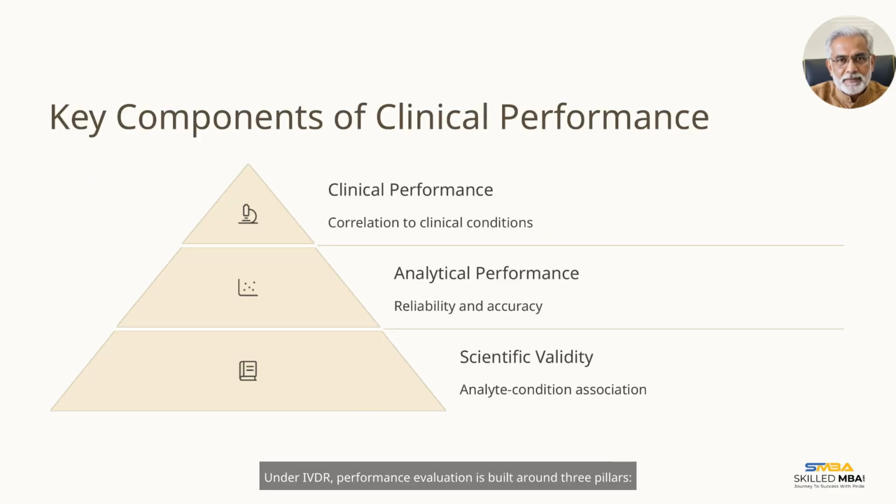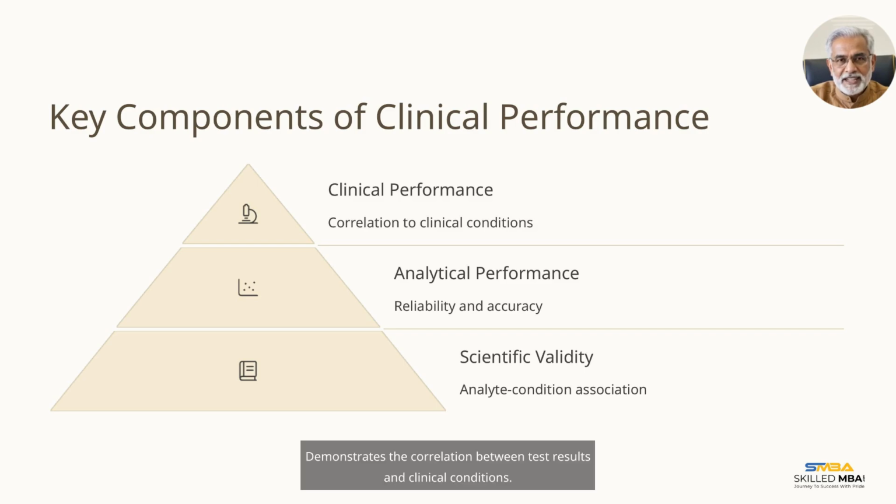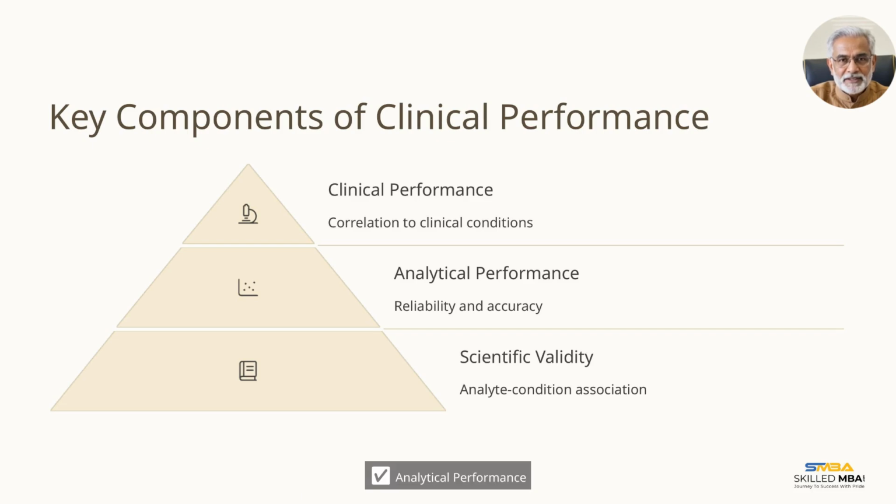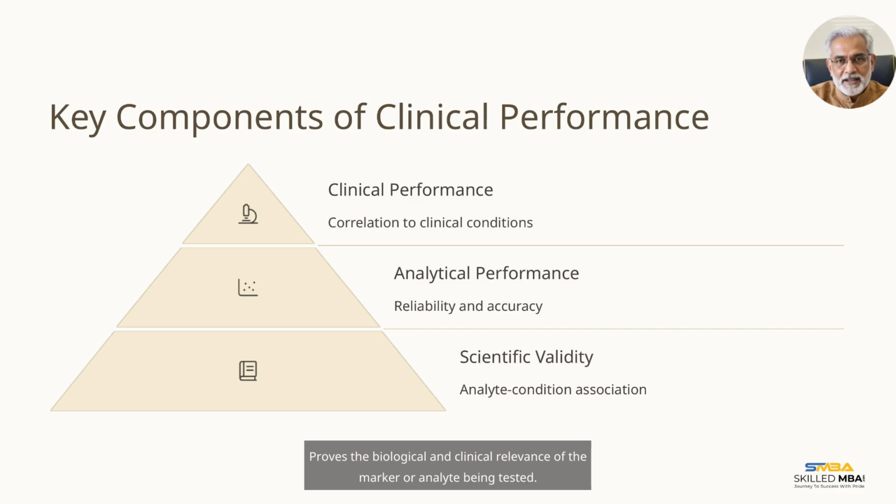Under IVDR, performance evaluation is built around 3 pillars. Clinical performance demonstrates the correlation between test results and clinical conditions. Analytical performance confirms accuracy, repeatability, and reliability of results. Scientific validity proves the biological and clinical relevance of the marker or analyte being tested. Together, these elements ensure a device is fit for clinical purpose, in both lab and real-world settings.